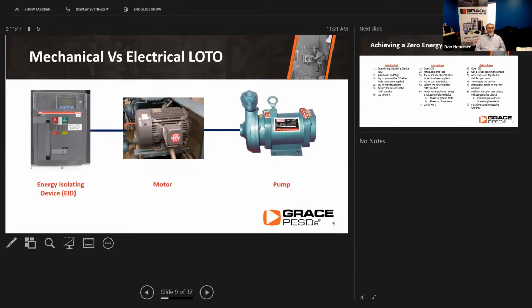The best practice to do that would obviously be to isolate the motor from the source. So we're going to go ahead and disconnect it, throw the energy isolating device, throw the disconnect, and then make sure there is no stored energy anywhere, and then go ahead and make that adjustment at the motor and tighten it back up.